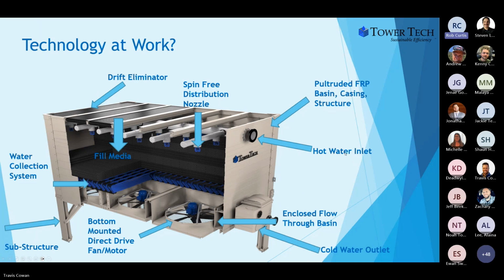We're going to act like a drop of water flowing through the tower. If you start at the hot water inlet connection that you see there, we flow water through a traditional header lateral system that you would have in a counterflow design, but then it hits our spin-free distribution nozzle. This distribution nozzle is different than other distribution nozzles in that it has a large orifice design. Traditional nozzles are typically 1/2 inch to 3/4 inch opening. Our nozzle's 2-inch opening.